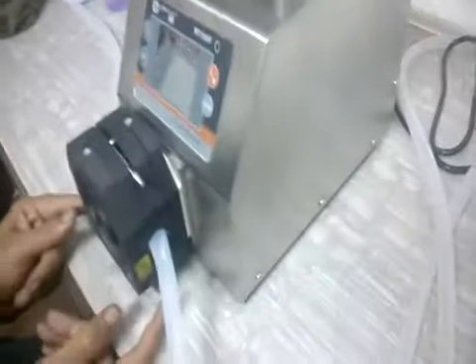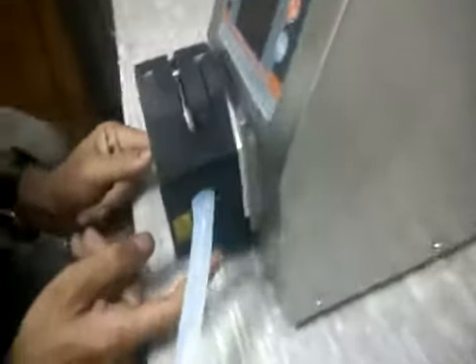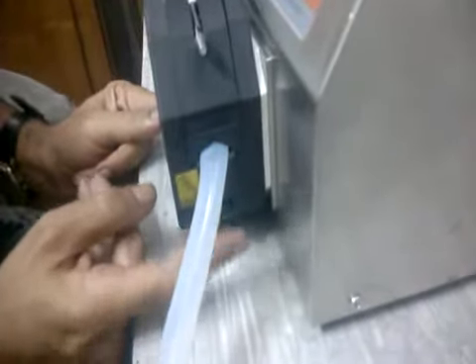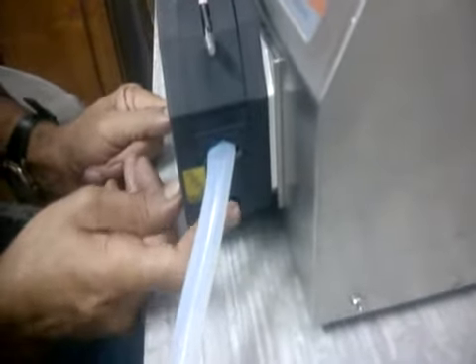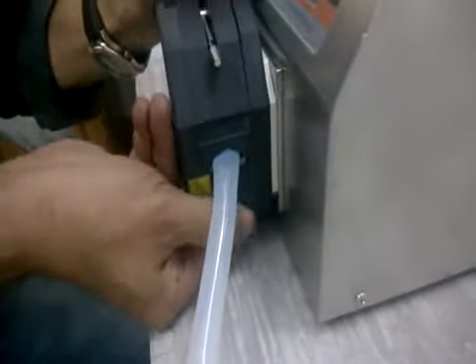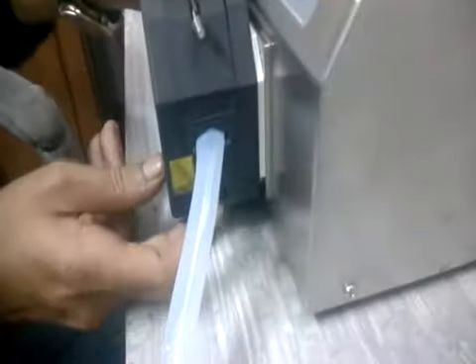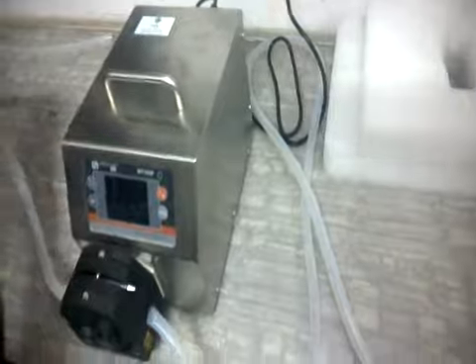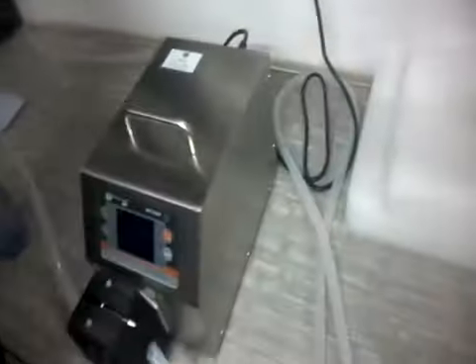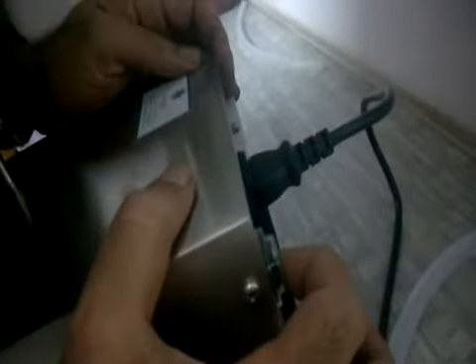And on the other side also it is like this. If you load some other tubing, with the help of this screw you can adjust the distance and move it up and down. So here we are leaving it for 36. Okay, now the tubing is loaded and I am putting this tube in the source and that is your waste. Just put the power on to the machine. On the back side there is one on-off switch. Put it to 1 and the machine gets energized.